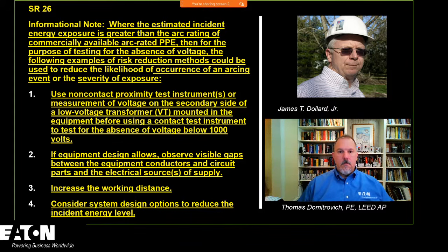And it basically says where your exposure is greater than the arc rating of commercially available ARC-rated PPE. Then, for the purpose of testing for the absence of voltage, the following examples of risk reduction methods could be used to reduce the likelihood of occurrence of an arcing event or the severity of exposure. And keep in mind, all right, it's risk reduction methods. We have hazards. You can't reduce the hazard. You can only reduce the associated risk.